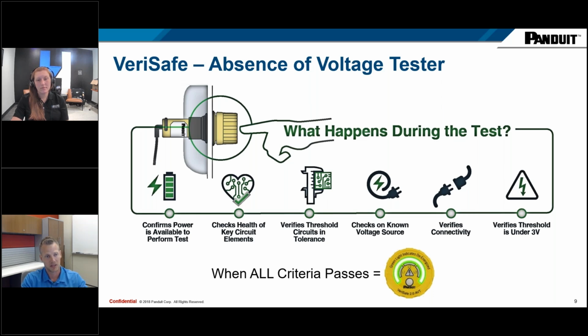It goes through and checks the health of the circuit elements. Very much like when you turn on your computer, it goes through and checks all the communication between the motherboard and the hard drive and the RAM and all that. That's about the extent of my knowledge about that, but if it fails, it's going to give you safe mode or an error that, hey, something's not right. VeriSafe does the exact same thing. It makes sure that the threshold tolerance and the circuits are in place, and it's able to measure right around that 3-volt threshold, which is in UL 1436 as the safe or unsafe threshold.